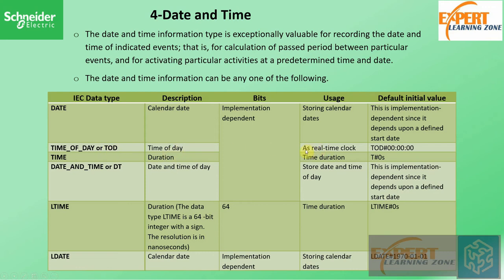The Time of Day type is used as a real-time clock; its default value is zero hours, zero minutes, zero seconds. TIME is a time duration that is implementation dependent with a default value of zero seconds. LTIME can go up to 64 bits — it is a 64-bit integer with resolution in nanoseconds, also a time duration with default value zero seconds.